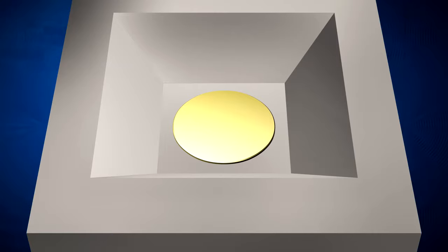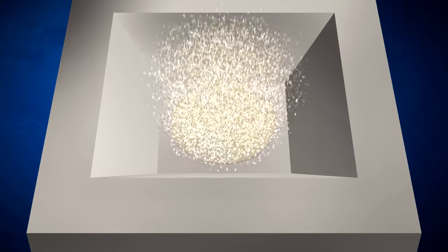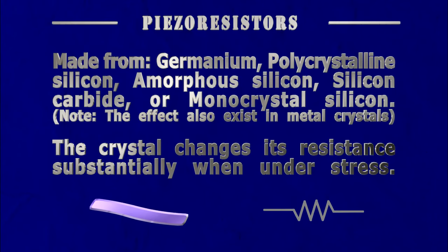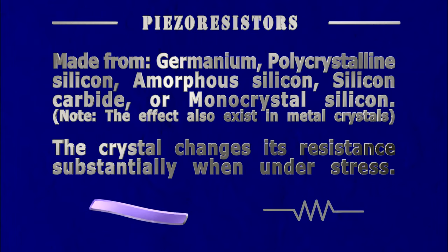If that sounds like just the worst, don't worry, there is a better way. Allow me to introduce you to the world of piezo resistors. This topic might be a little bit wild, but I'd be remiss not to talk about it since most pressure sensors use it nowadays. Let's back up a few steps before we made the capacitor plates, and instead deposit this funky material called a piezo resistor. These strips, sometimes made out of the following materials, change their resistance under stress.